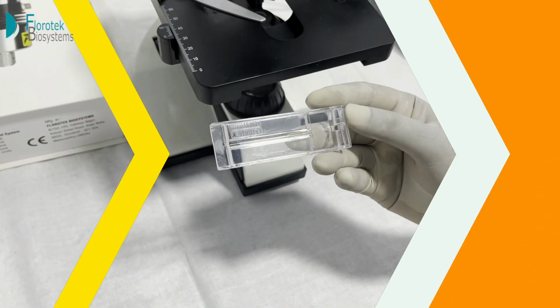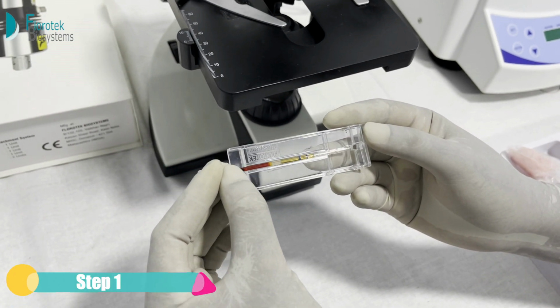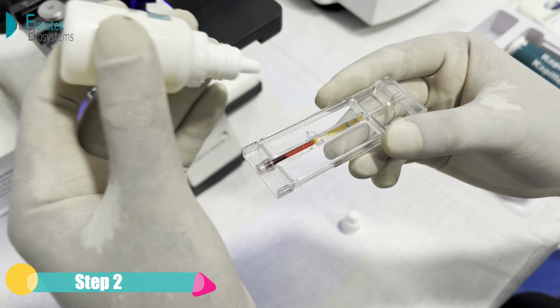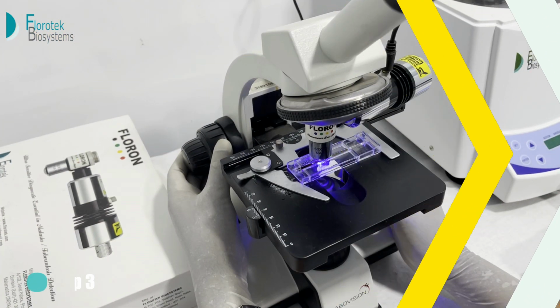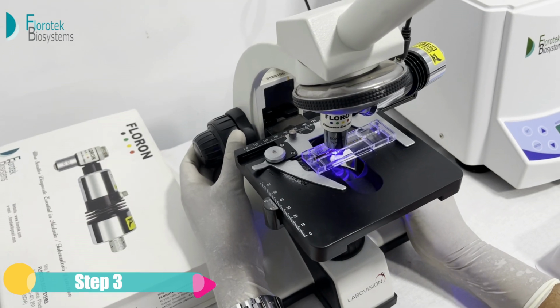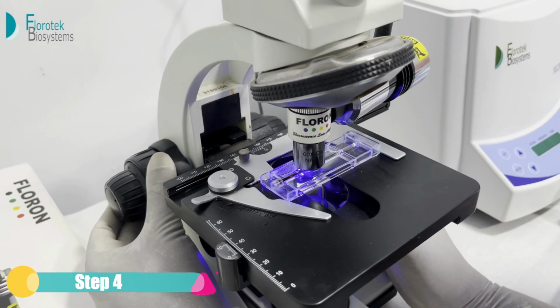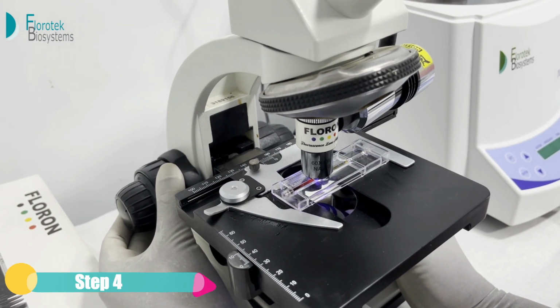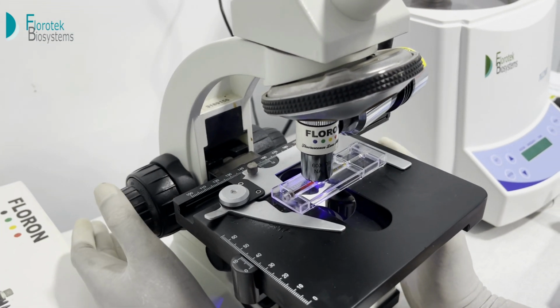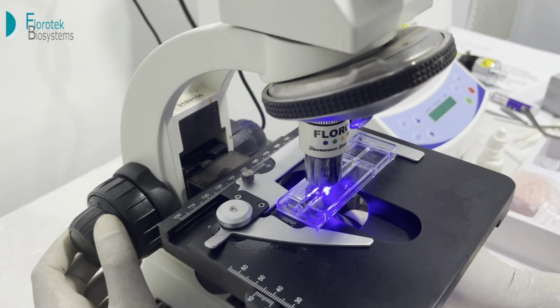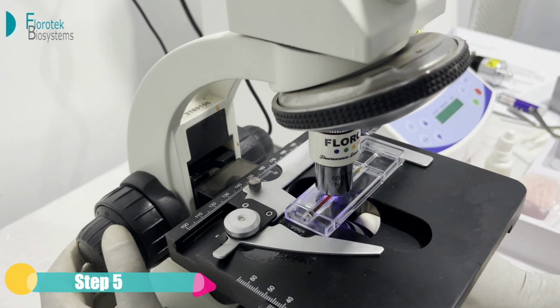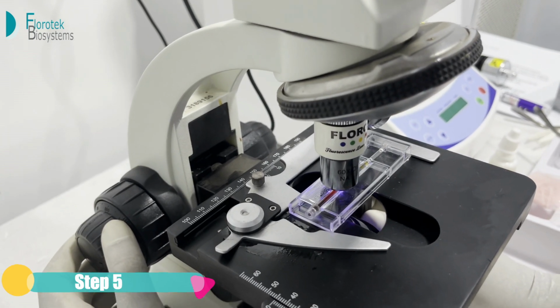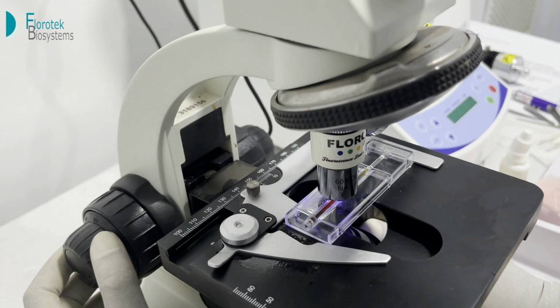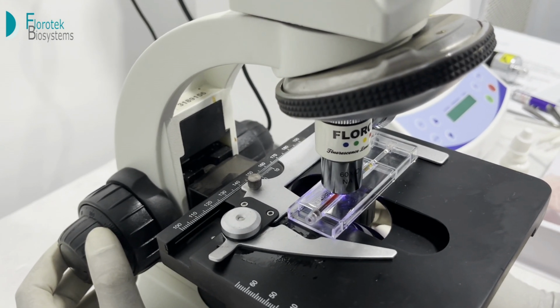Let's understand how to focus the capillary tubes. Tube is placed in a specially designed capillary holder. A drop of immersion oil is put exactly at the interface of RBC and buffy coat. Allow the blue light to center on top of the tube. Slowly bring down the objective lens to dip the same in the immersion oil while taking care not to crash the lens into capillary tube. Using microscope adjustments, focus the tubes in such a way that blue light goes completely into the capillary tube. Make sure you get the area of observation under complete focus.